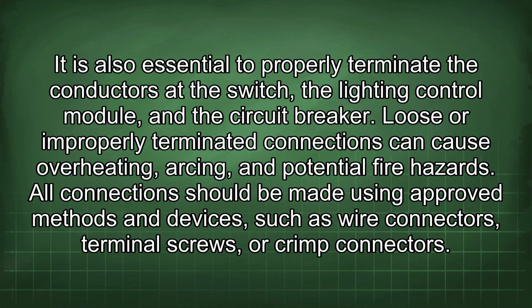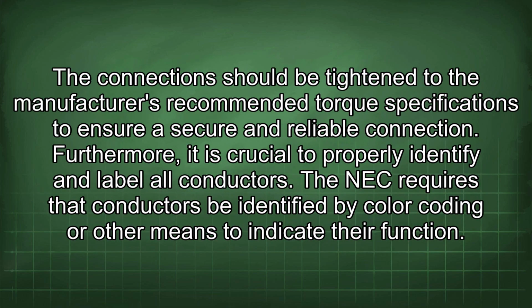It is also essential to properly terminate the conductors at the switch, the lighting control module, and the circuit breaker. Loose or improperly terminated connections can cause overheating, arcing, and potential fire hazards. All connections should be made using approved methods and devices, such as wire connectors, terminal screws, or crimp connectors. The connections should be tightened to the manufacturer's recommended torque specifications to ensure a secure and reliable connection.